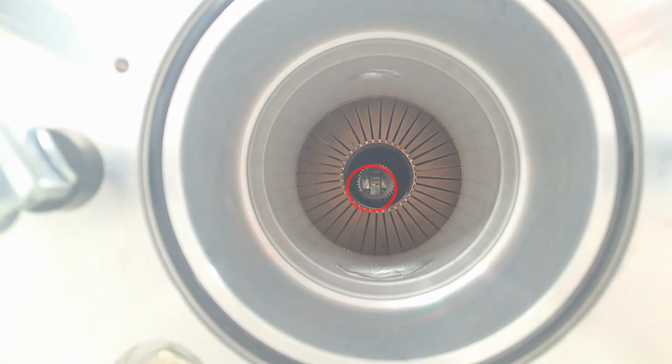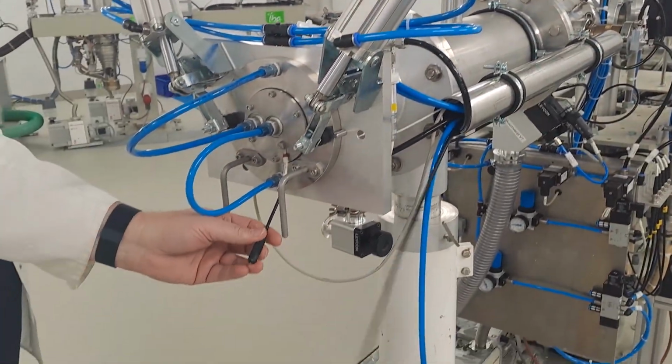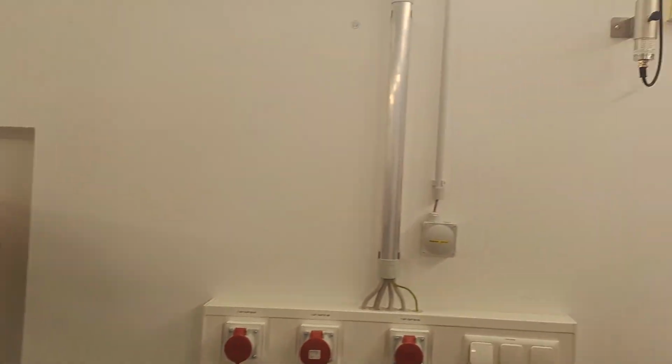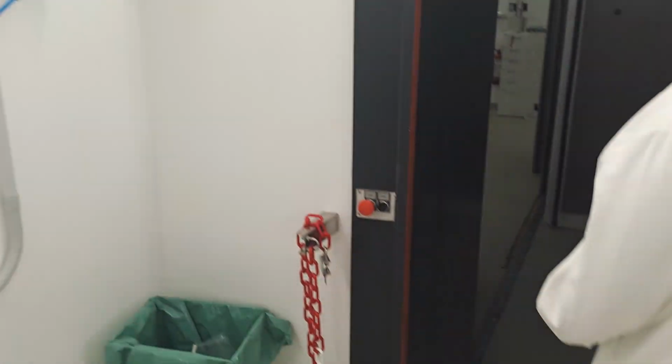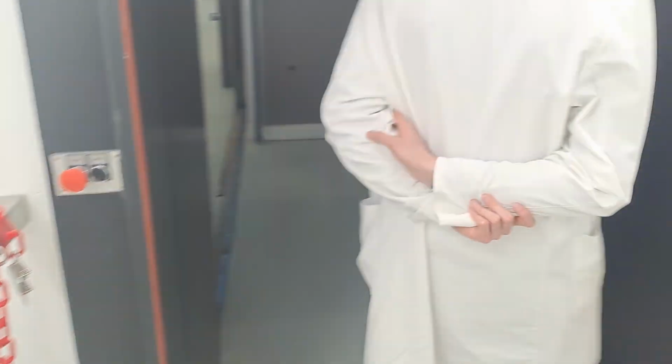Looking inside such a beamline, you can also see the 4-sector aperture. The target can then be reattached, vacuum be drawn, and then irradiated again, but only after everyone has left the room. I hope now we have a better understanding of how a cyclotron looks and how it works.